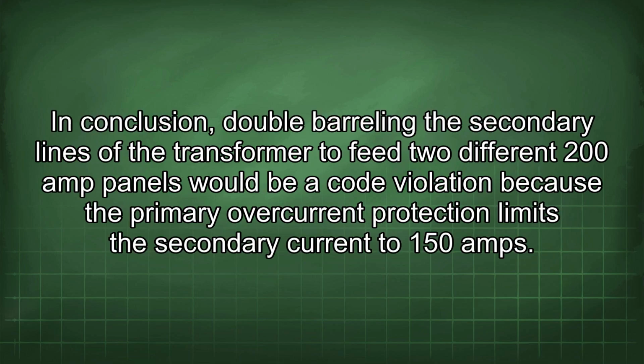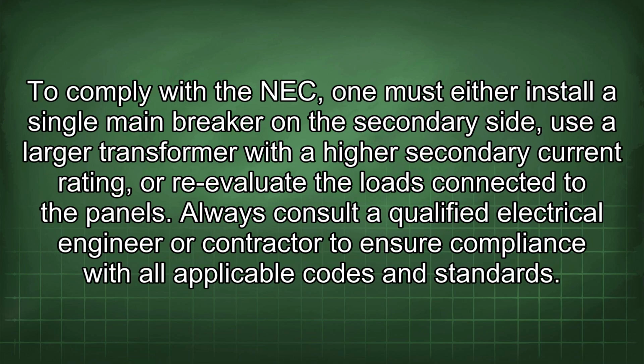In conclusion, double barreling the secondary lines of the transformer to feed two different 200 amp panels would be a code violation because the primary overcurrent protection limits the secondary current to 150 amps. To comply with the NEC, one must either install a single main breaker on the secondary side, use a larger transformer with a higher secondary current rating, or re-evaluate the loads connected to the panels. Always consult a qualified electrical engineer or contractor to ensure compliance with all applicable codes and standards.